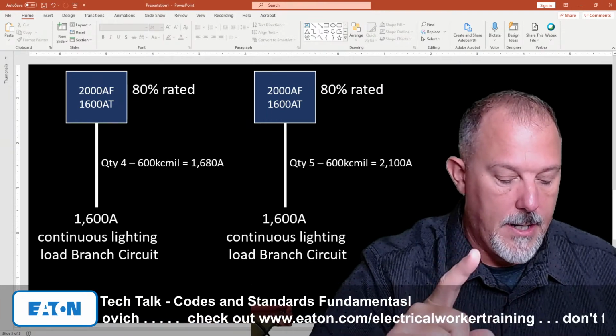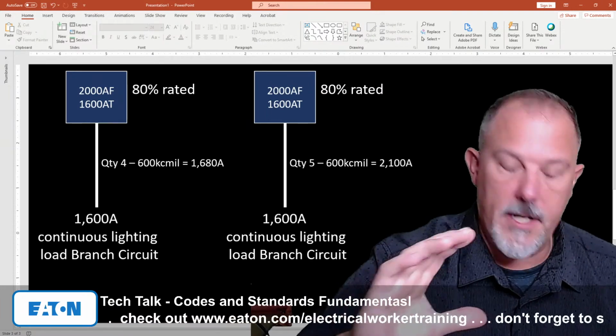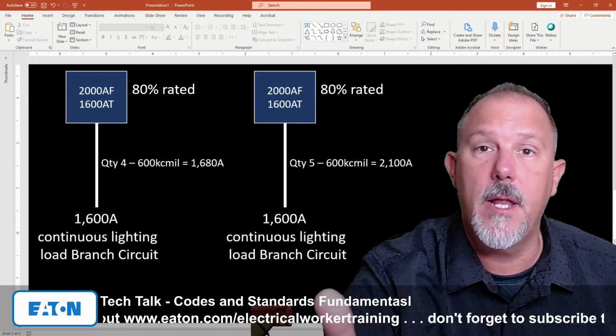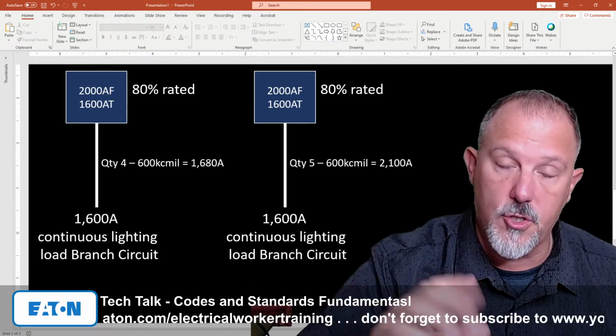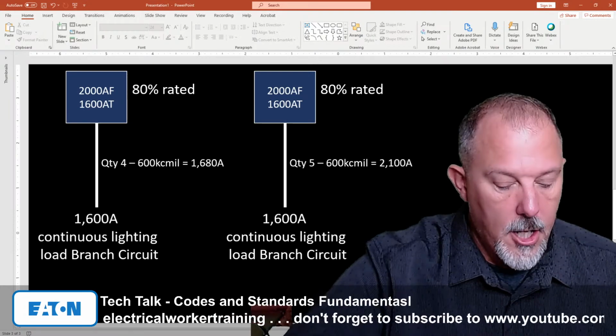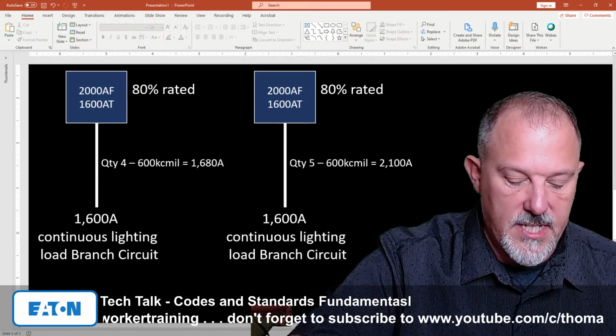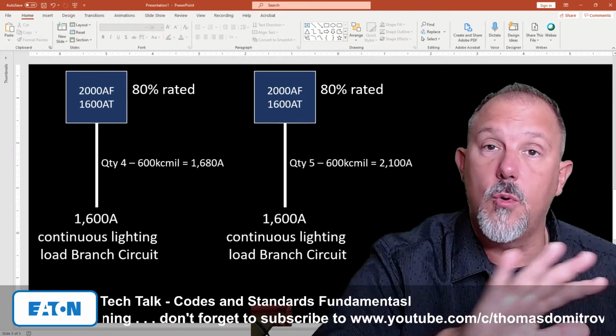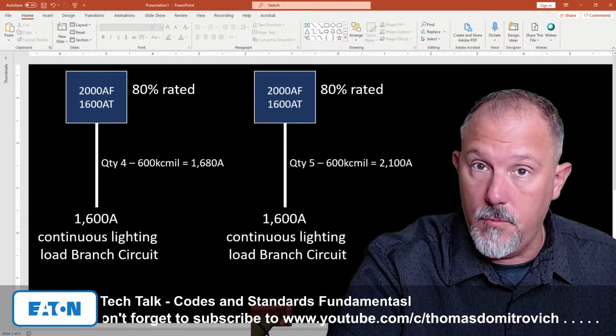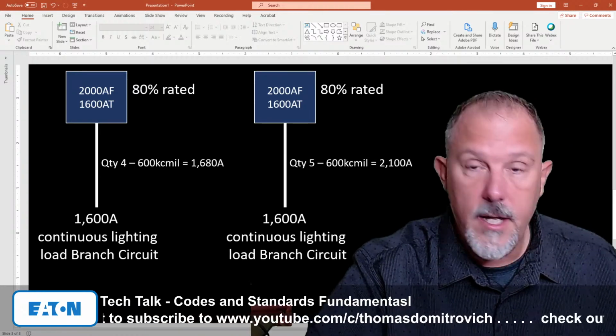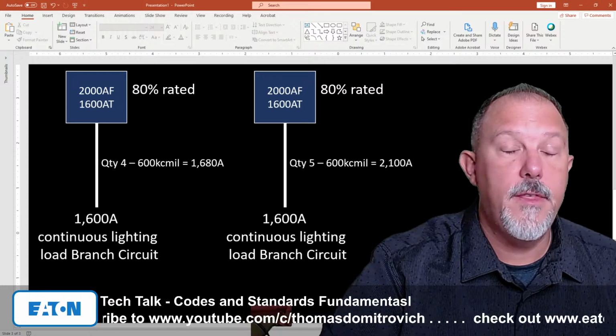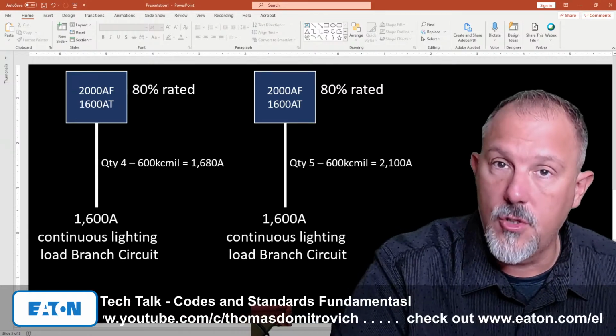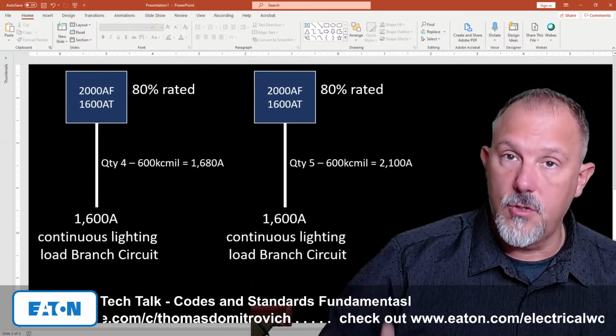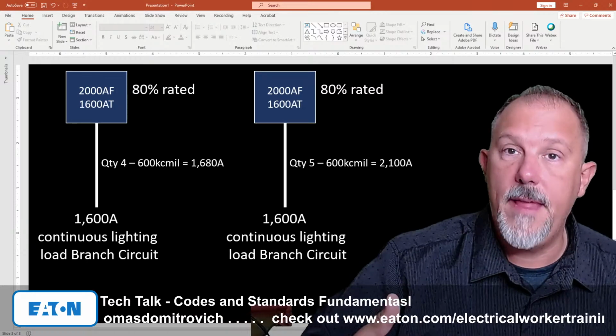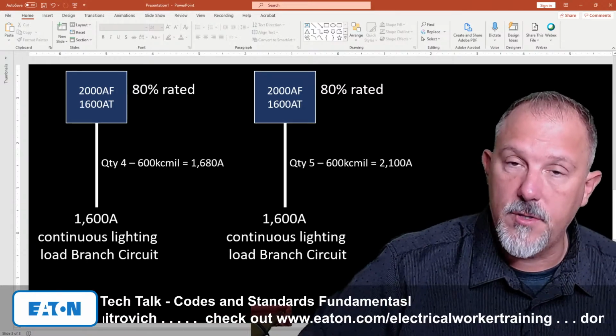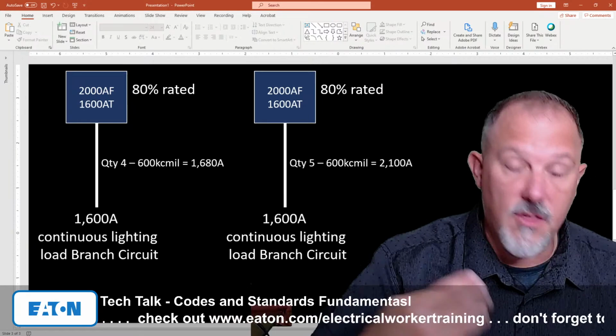It can be located behind bolted equipment enclosure doors. So that would be like an industrial control panel where you have a bolted door. Or located behind locked doors, accessible only to qualified persons. That could be the door of the panelboard. It could be the door of the room. It doesn't say which door. If I lock the room and the panelboard is in the room, even though the door of the panelboard is not locked, if I lock the door going into that room and that door is only accessible by qualified persons, then I meet 3.